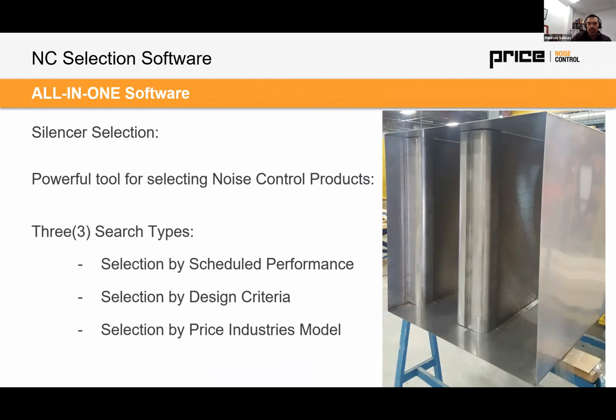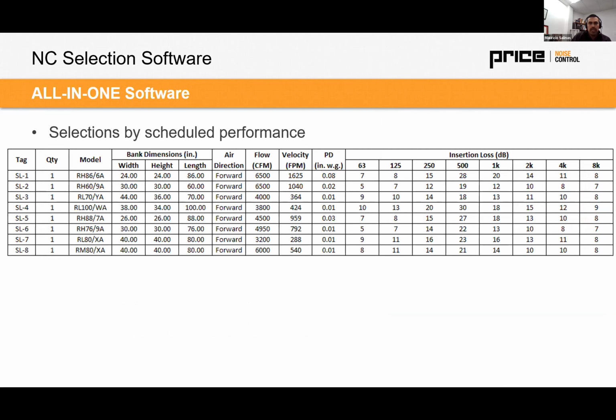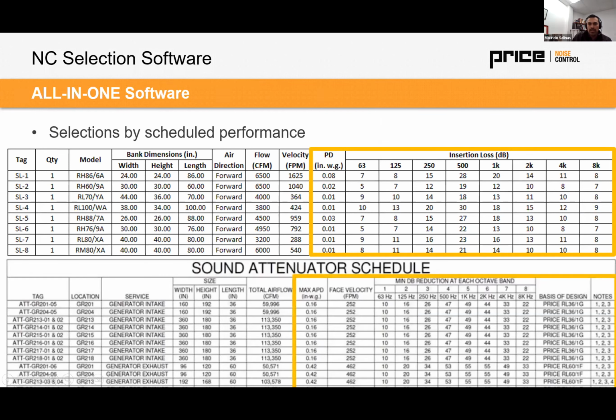And then for more expert users, you might be able to select by model or do an acoustic analysis to specify the performance required, or that performance that goes into a schedule. Typically, when you're selecting by performance, an acoustician already did an acoustic analysis, which means you have the minimum insertion loss required to get to an NC level in the space. You have airflow, you have models, you have sizes. So that's number one, right?